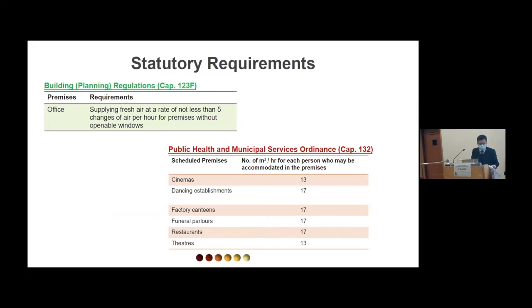For example, the Building Ordinance promotes the use of natural ventilation as it sets minimum requirements of openable windows. However, it's not often that we have openable windows in commercial buildings in Hong Kong. Even if it does have such provision, its operation is largely dependent on occupants' behavior, especially in the cold season. As such, the Building Planning Regulations state that if you cannot satisfy the openable windows requirement, then a mechanical means of ventilation, which shall be capable of supplying fresh air at a rate of not less than 5 ACH, is required for offices. It is important to note that the 5 ACH of fresh air does not necessarily mean that the entire room has an ACH of 5.